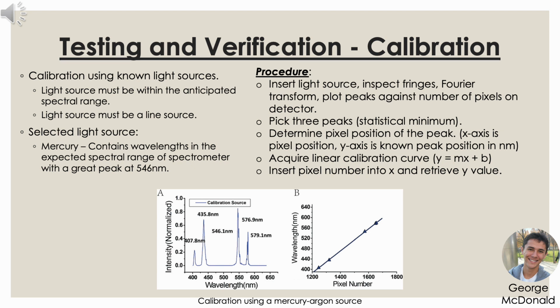But the basic idea is you would insert your light source, and then you would produce your fringes, go ahead and image process them, and while you're at it, go ahead and plot the peaks that you obtain from that Fourier transform against the number of pixels on the detector. Then you would pick 3 peaks, which is a statistical minimum, and determine the position of the peak at the pixel as well as at the known wavelength in nanometers. So in this case, the x-axis would be pixel position, and the y-axis would be the known peak position in nanometers.